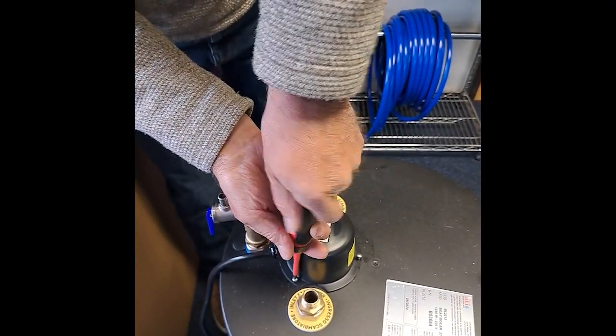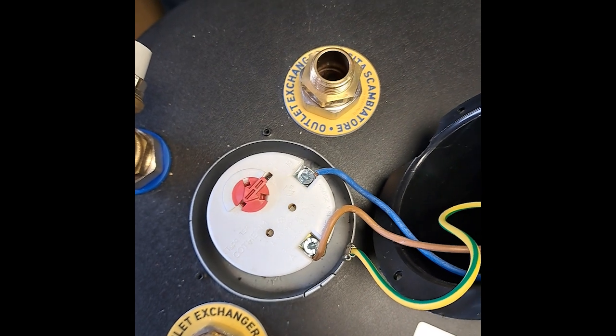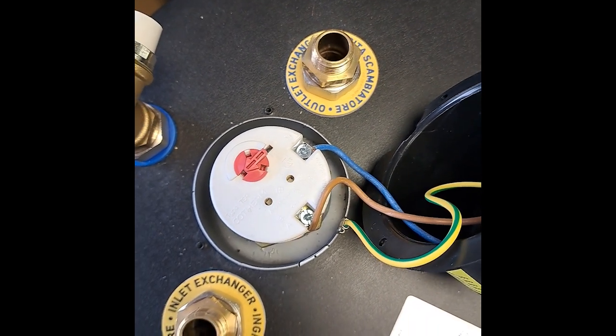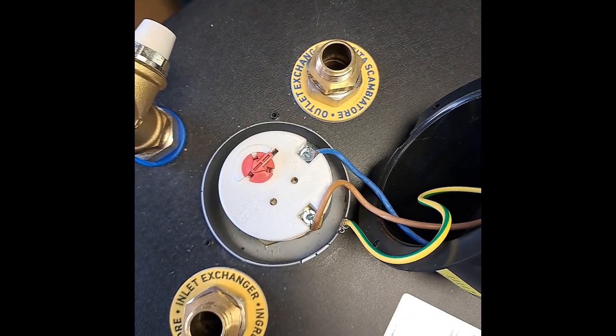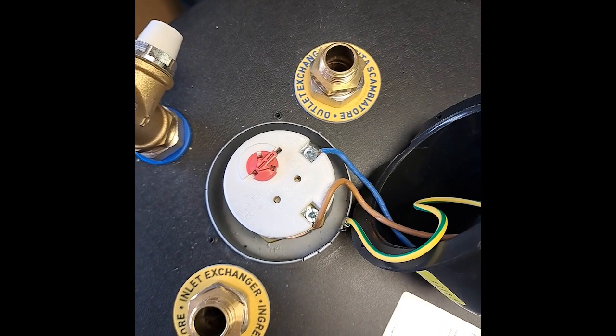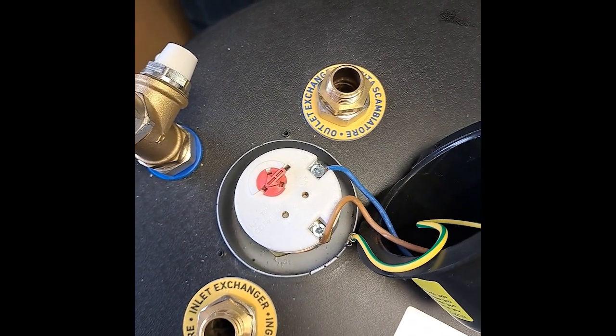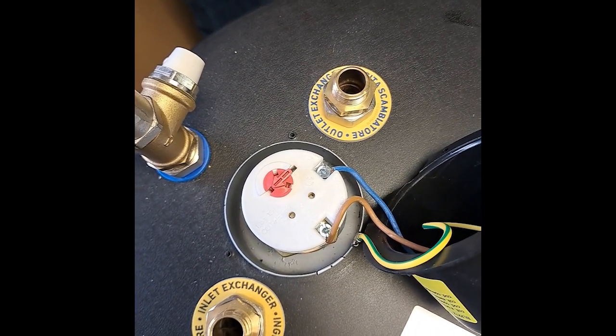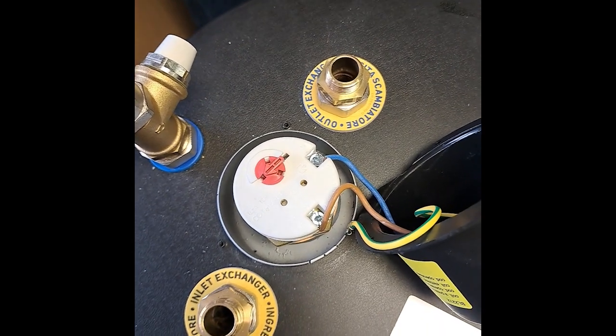Now the cover is off, you can clearly see the wiring. The live and neutral wires are connected to the thermostat, and the ground wire is attached to the body of the calorifier. At this point, it may be worth taking a photo of the connections to remove any doubt when you put it back together.